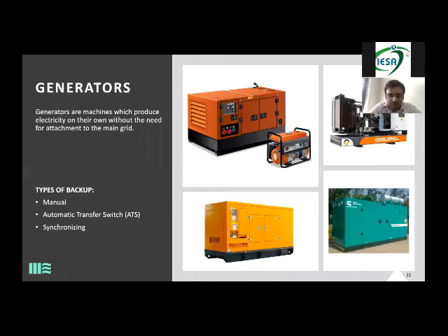Okay. Last question. How much load is actually needed for a 100-ton air conditioning for an event? The calculation from ton to kilowatt depends on equipment to equipment. The normal calculation is that you multiply tons by 1.6 or 1.75. It depends from machinery to machinery, but this is the normal calculation which everybody is using as of now. The range is 1.6 to 1.75, and you'll get kilowatts. Yeah, for the safer side we usually take it as 2. It can be taken, but 2 is always on the very higher side. 1.75 is good enough for any kind of air conditioning which is coming on site.